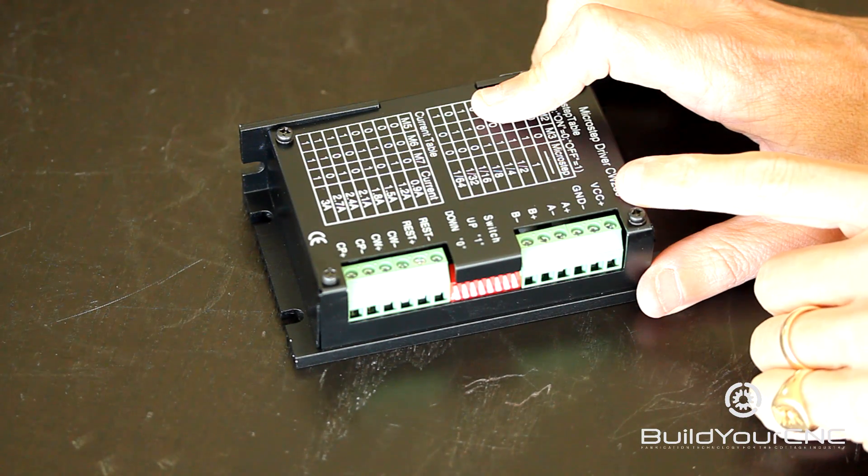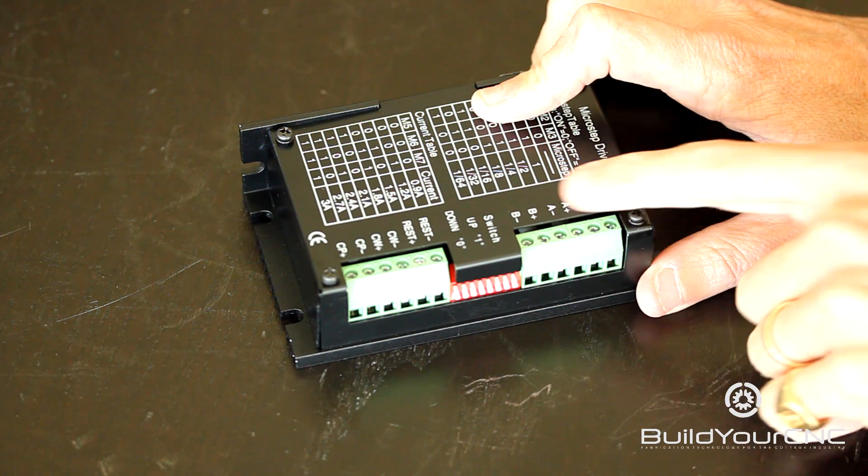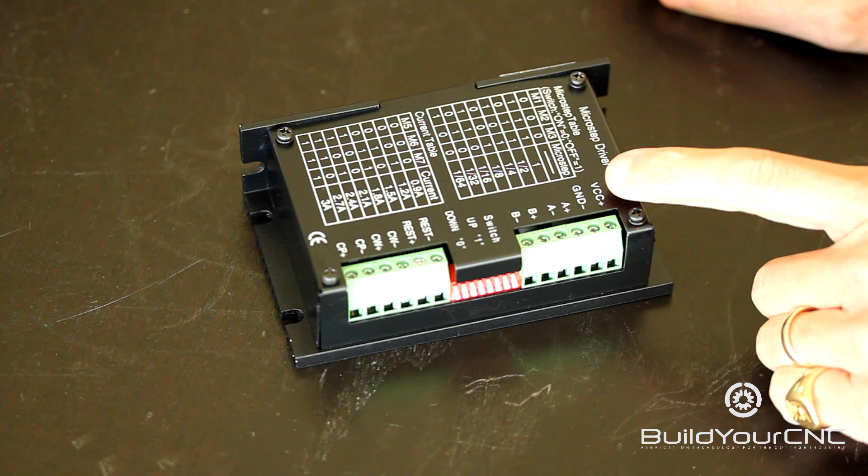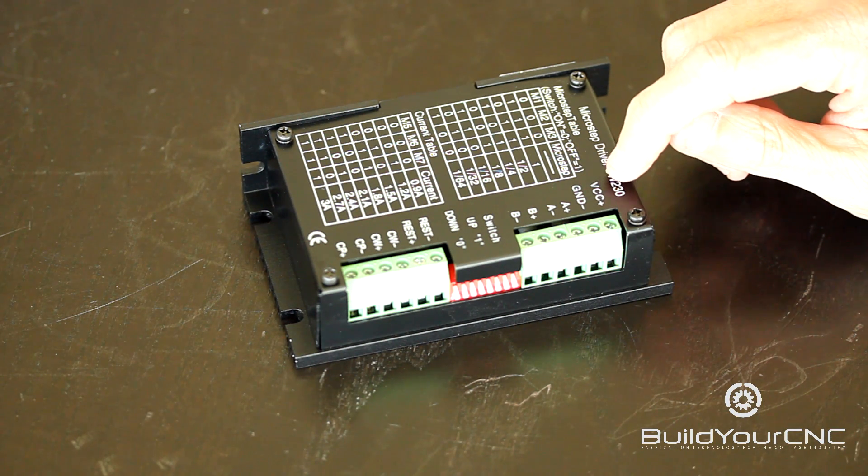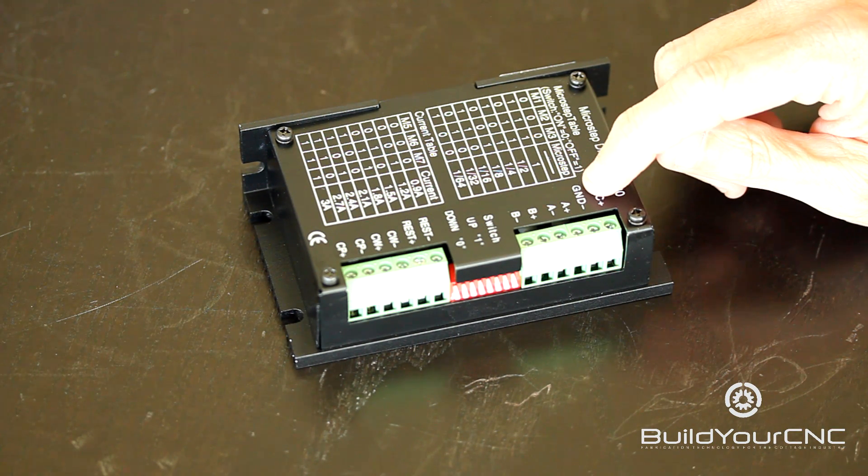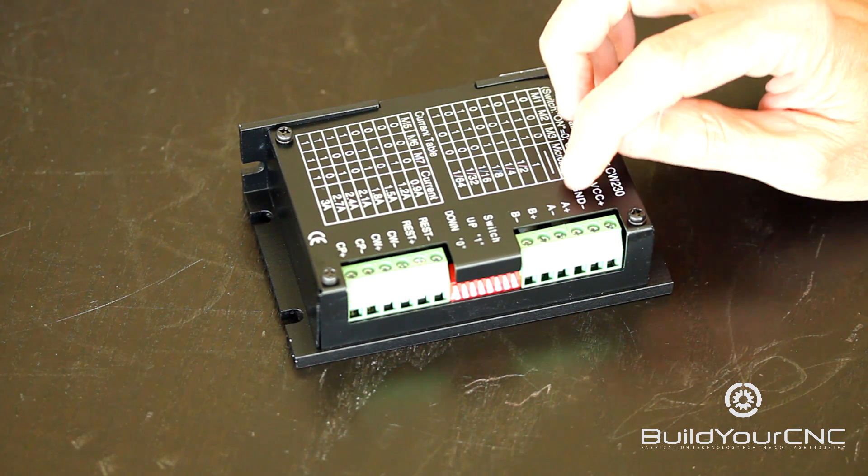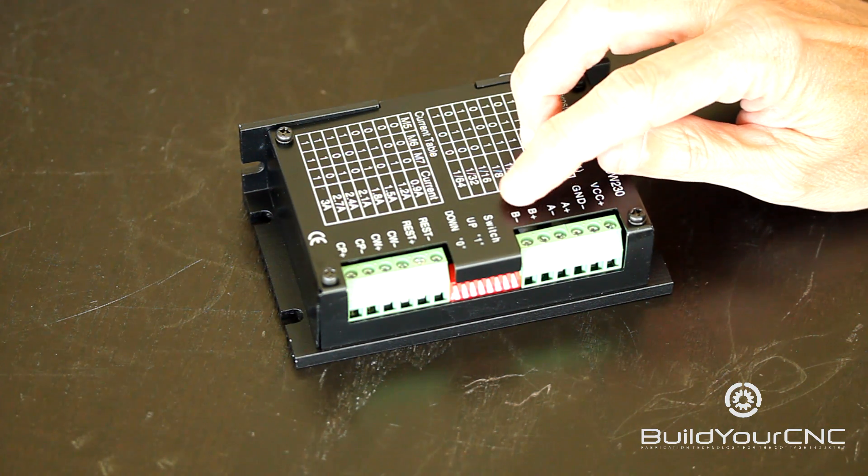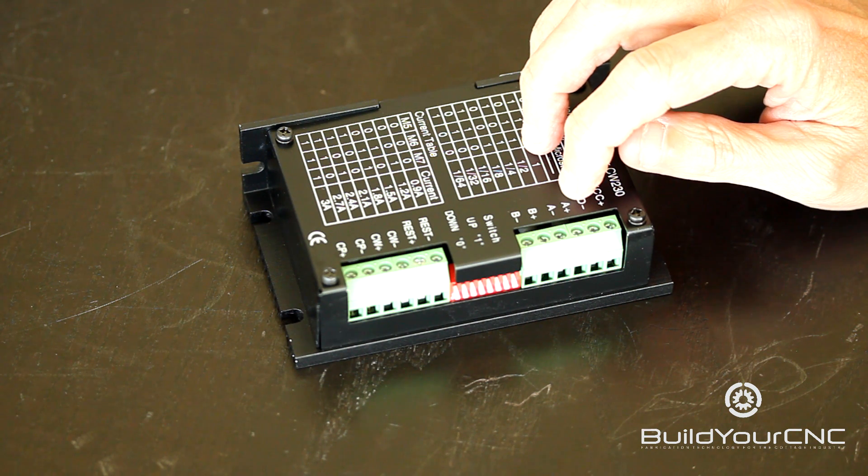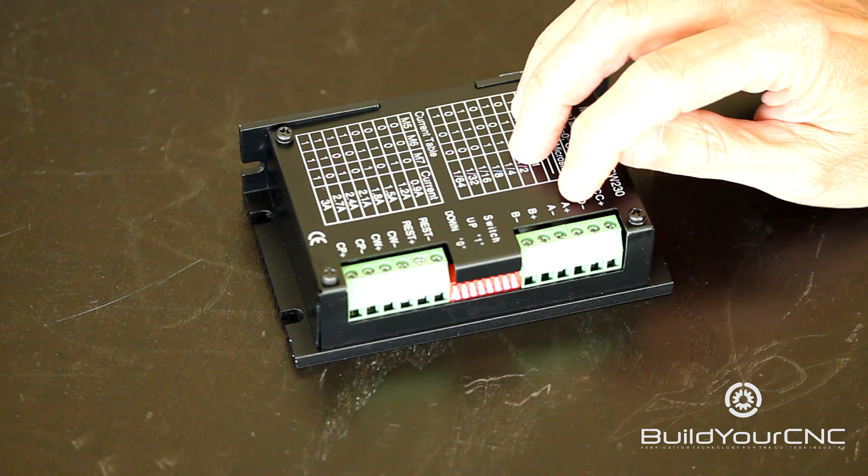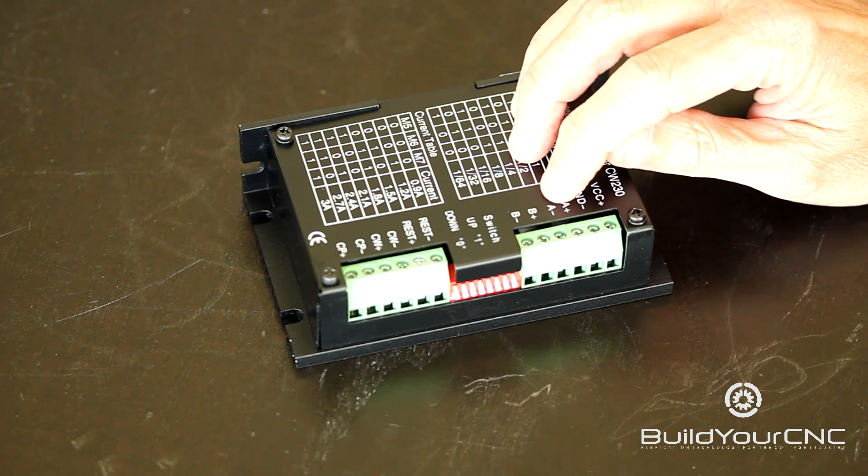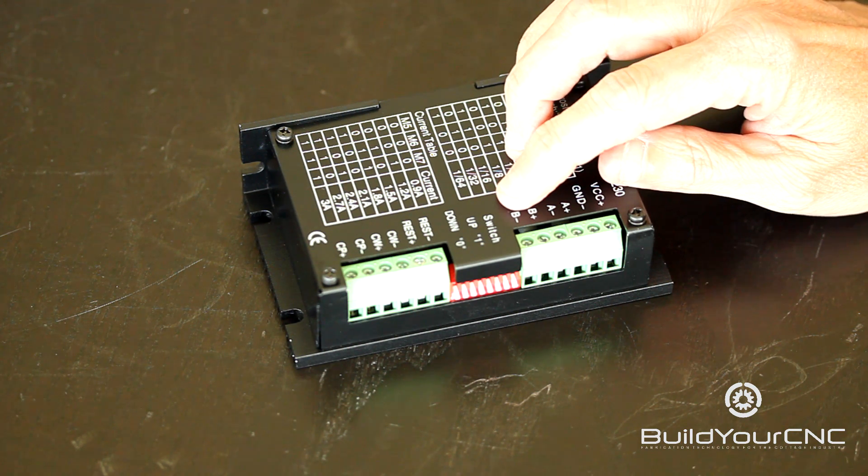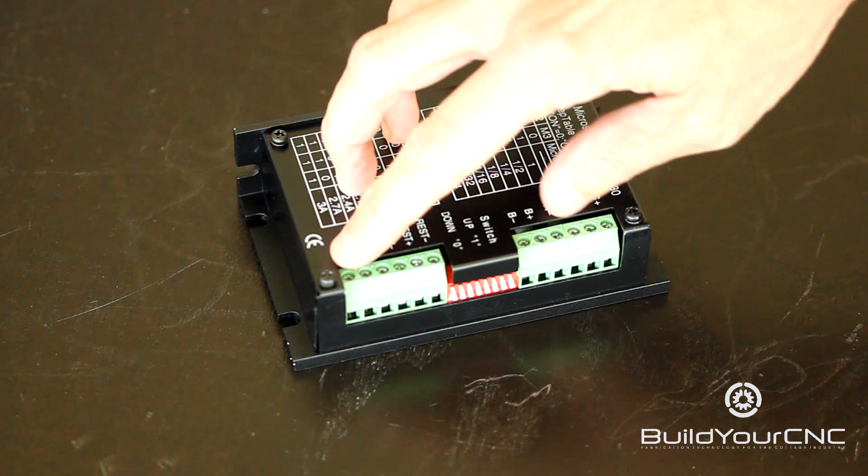The first two terminals on the motor output side provide power from a power source like a power supply. The range of voltage you can apply to these terminals is 24V to 40V. The A+, A-, B+, B- is connected to the motor coils and generally stepping motors have two coils. A+, A- would be on one coil and B+, B- would be on another coil.